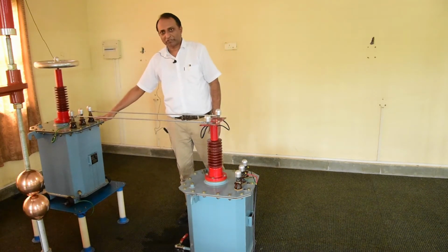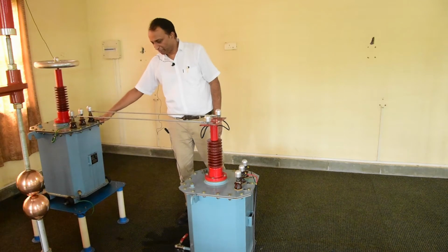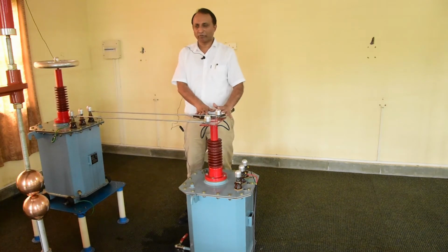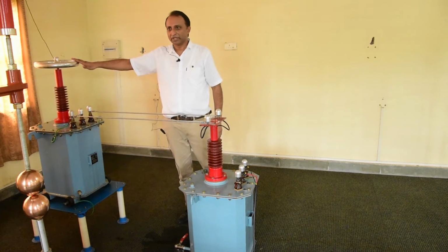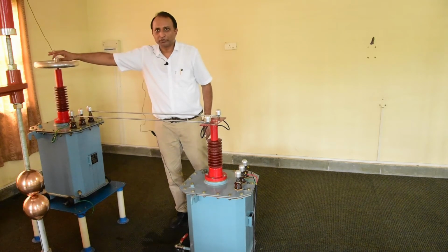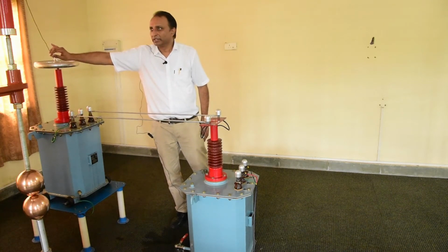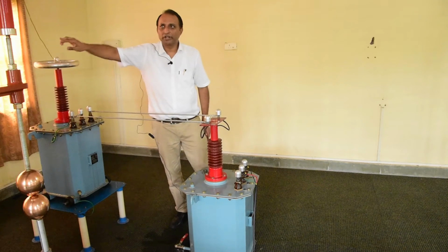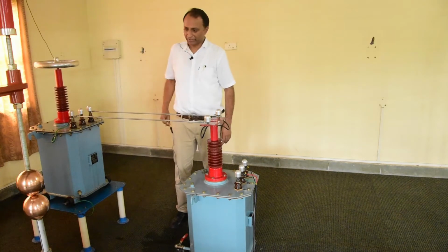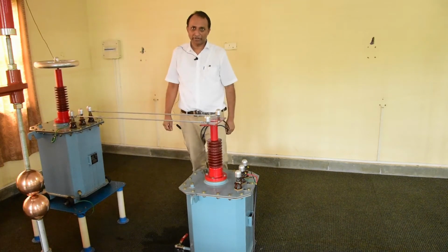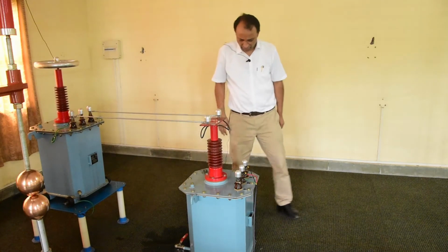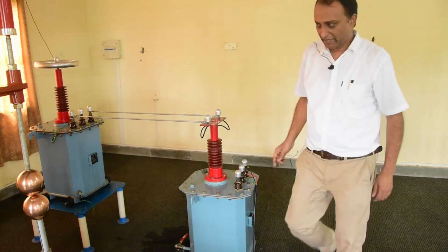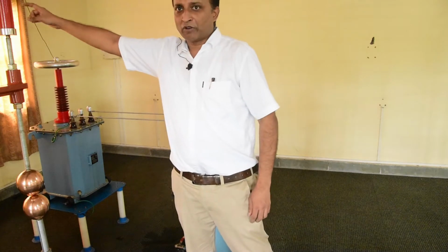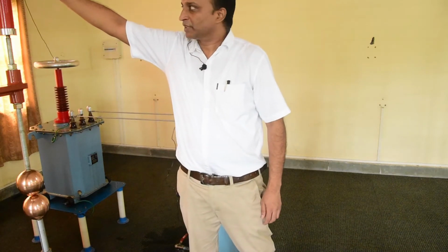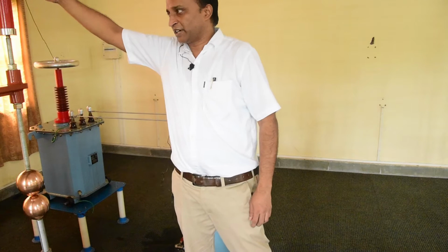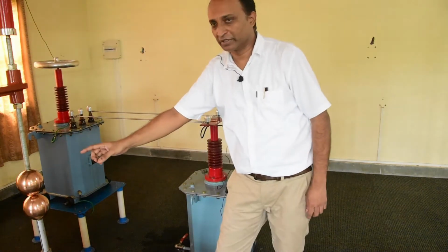The individual output of this transformer is 50 kV, but this 50 kV coming in series with the 50 kV from the first stage, we get 100 kV. This will be connected through a thin conductor all the way to the upper electrode of the sphere gap. That sphere gap is partly visible here in our frame, right? So the output is coming all the way from the cascade transformer to the sphere gap. So this is the sphere gap assembly.